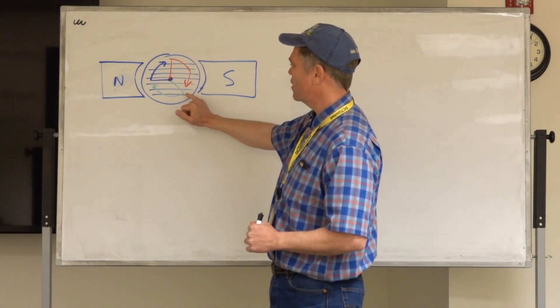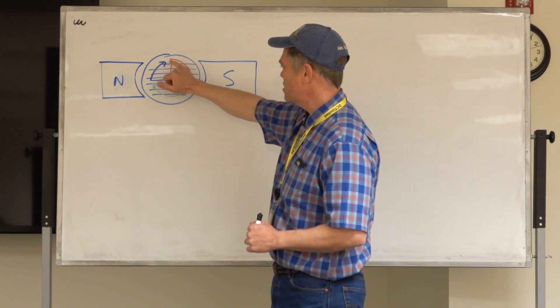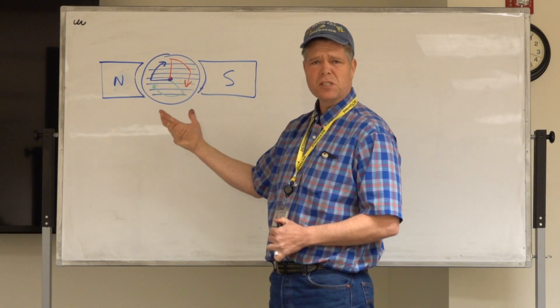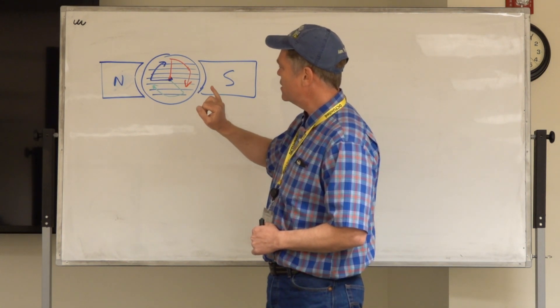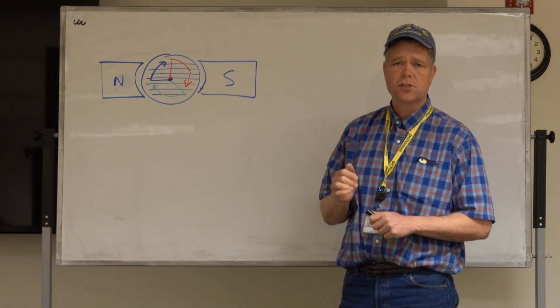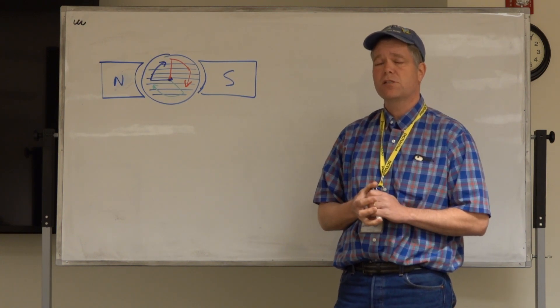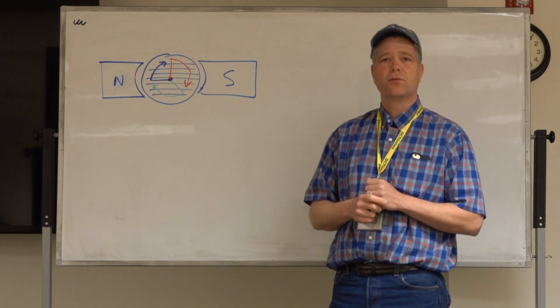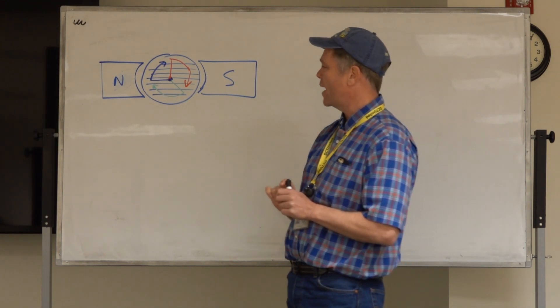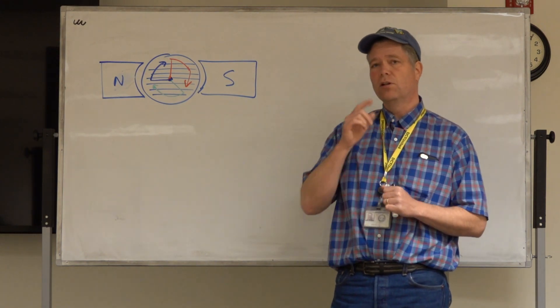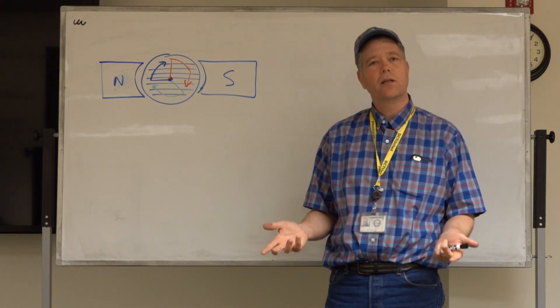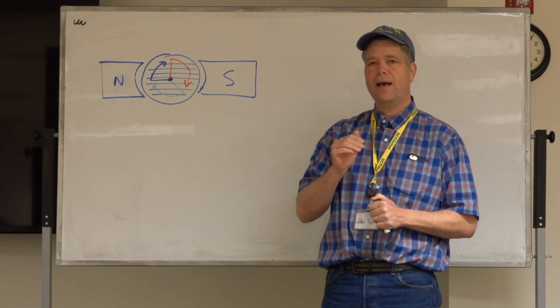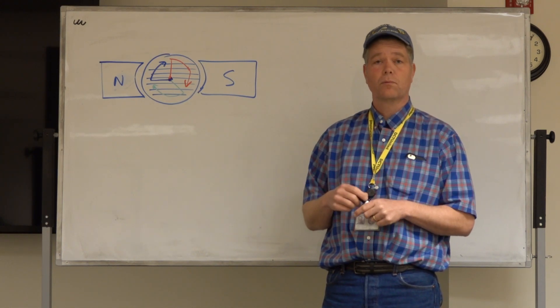As I'm cutting across the lines of flux in one direction, I'm developing a voltage across these conductors — loops of conductors spinning. Instead of having just one set of conductors, a three-phase generator or any generation system that creates three-phase power has three sets of conductors. Each one is a loop of wire spinning through that magnetic field. Each one is a third of the circle out of phase with the others. We divide a circle into 360 degrees, so cut into three pieces, that's 120 degrees each.